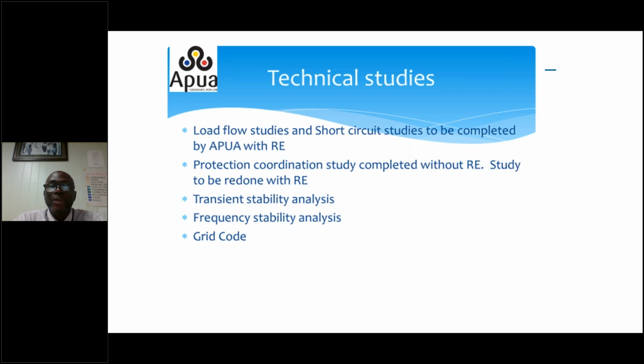And grid code, this is very crucial. We need to engage consultants to look at a grid code. The grid code basically dictates what amount of RE can be allowed in the system based on the characteristic of the system. It speaks to the protection setting, speaks to stability. It's a more comprehensive way of looking at it. Next slide, please.